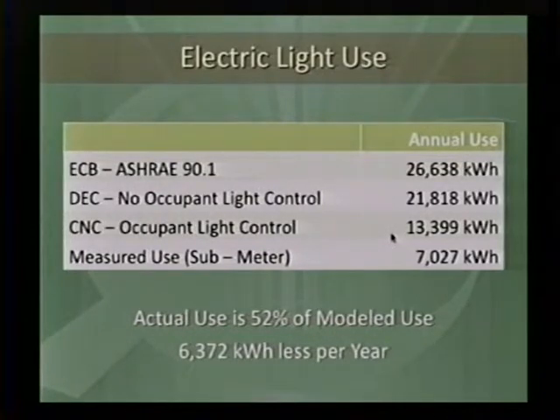We sub-metered lighting, and they generally don't turn the lights on. So compared to leaving the lights on all the time at almost 22,000 kilowatt hours, they're effectively only operating lights 1/3 of the time. This includes night. This is winter conditions. In other words, throughout the year, that's the amount of light usage in the building.